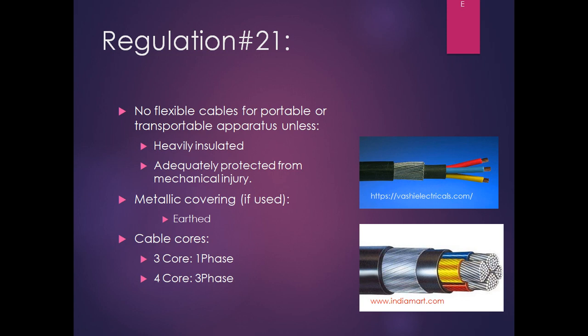because you are using some transportable apparatus, you may be in very near vicinity to the cable. If some spark comes out of the cable, personal injury may take place. That's why it is recommended that you bring the neutral core and earth core through the phase cores only. So preferably the neutral core should be laid through the phase cores. You can see for 3 phase red, yellow, blue and neutral, and for single phase you can take phase, neutral and earth cable. They should come through the same outer sheath. Of course the inner sheaths are different.